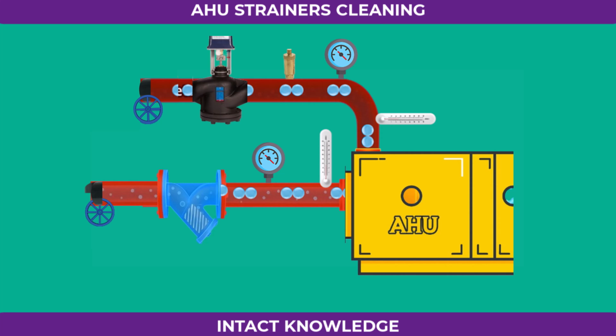Since the strainer was opened, air will now be trapped inside the line, and it must be removed before resuming operation. If the valve is opened without venting this air, it could cause air locking, restricting water circulation. Therefore, removing trapped air is an important step. To do that, slightly open the air vent located on the return line.